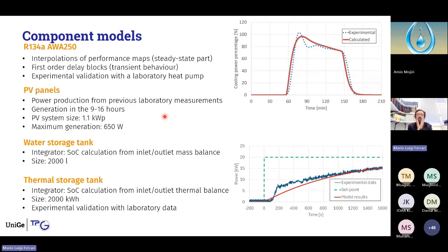First of all, we have developed some component models for components not available in the laboratory: the AWA250, the water storage tank, and the thermal storage tank. They were based on global balances, very simple models, because our analysis is related to the grid interaction, the grid economic balance, not to the specific details of the components. So we don't want to know the temperatures and pressures between some components of the AWA250, but the target is the global parameters in terms of cooling power produced, electricity consumed, and so on.